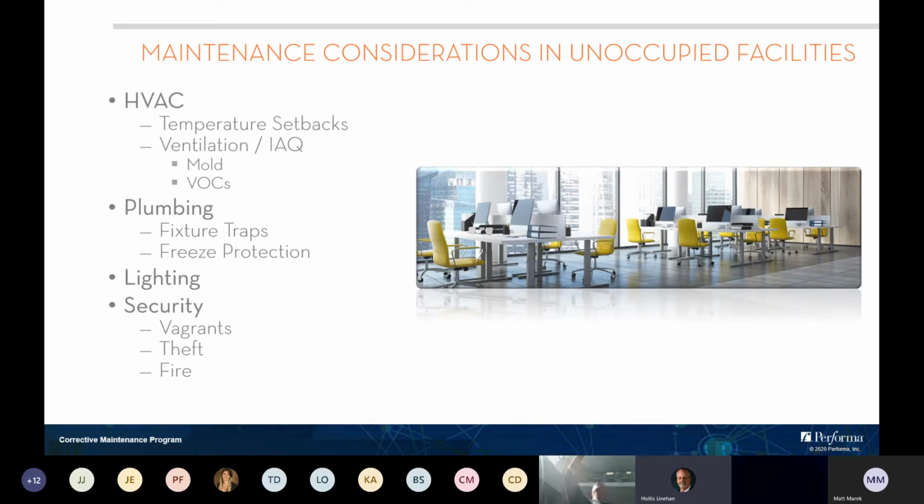And what they found was that dry traps within the building were taking human waste within the waste system, aerosolizing it, and it was getting into the interior spaces. And actually, they found some of the viruses on hard surfaces because of that transmission. So, when spaces aren't occupied, water isn't running in sinks, those traps can dry out, water in floor drains, those tend to dry out. So those are things we really need to understand and look at.